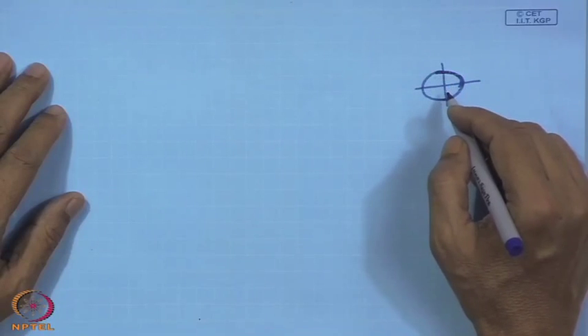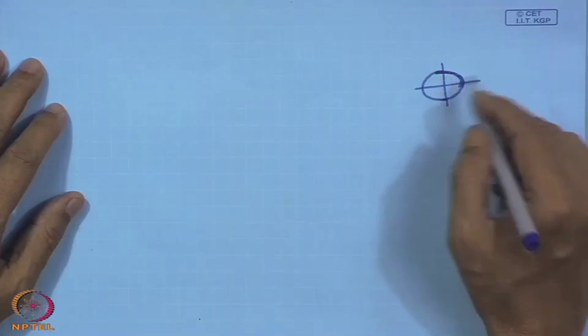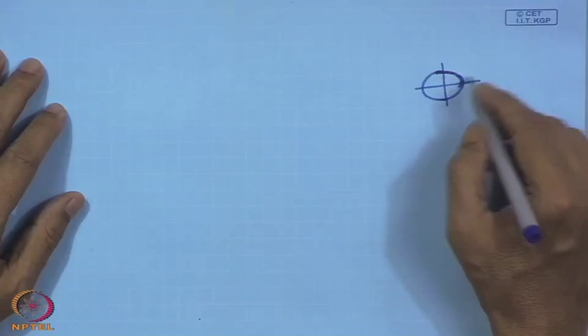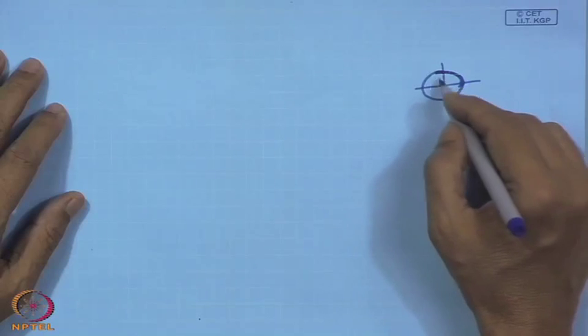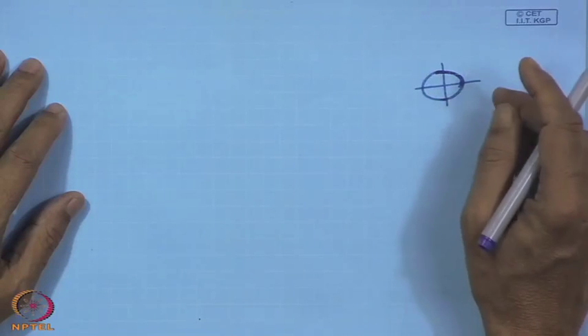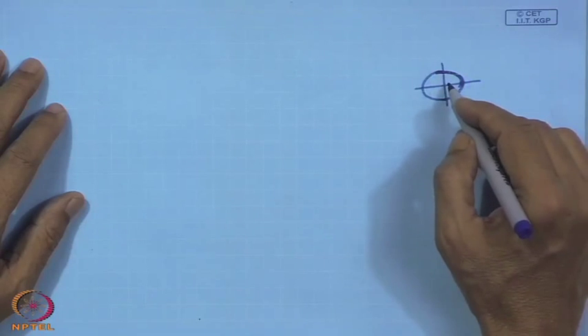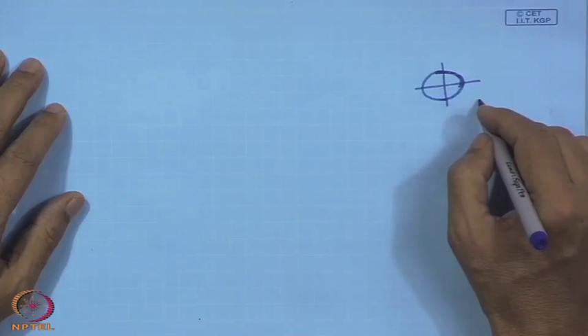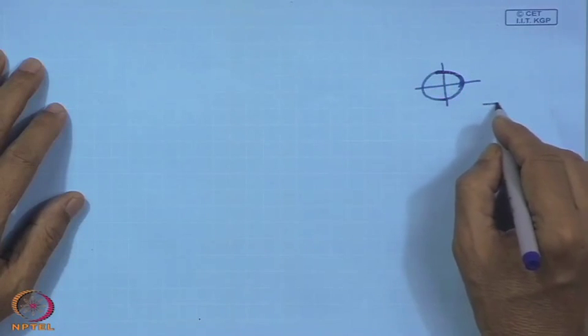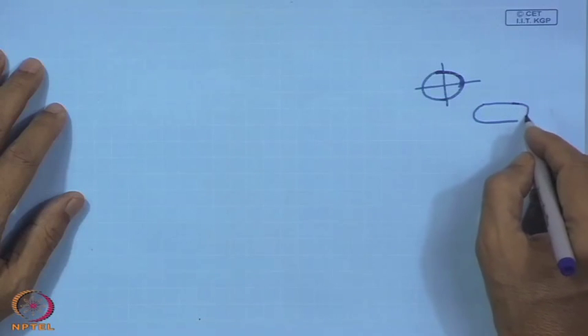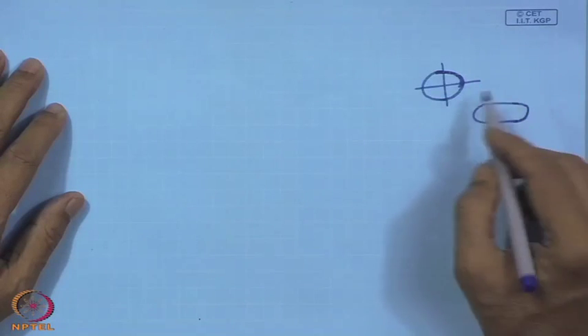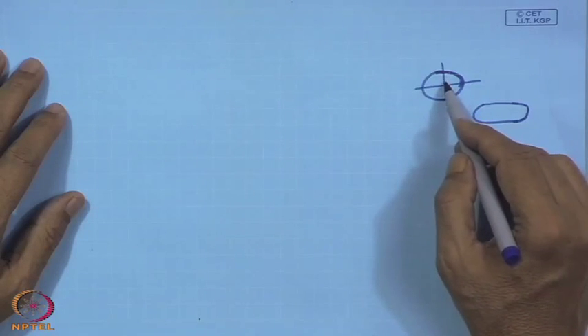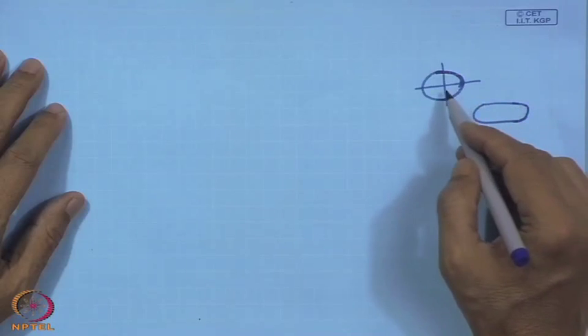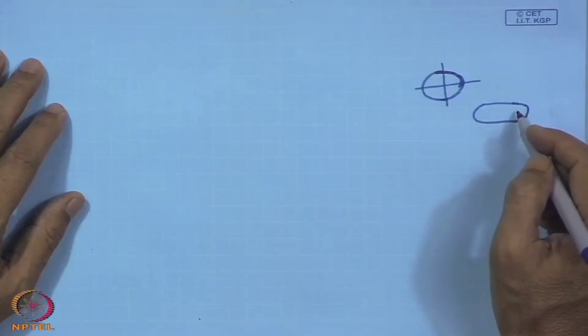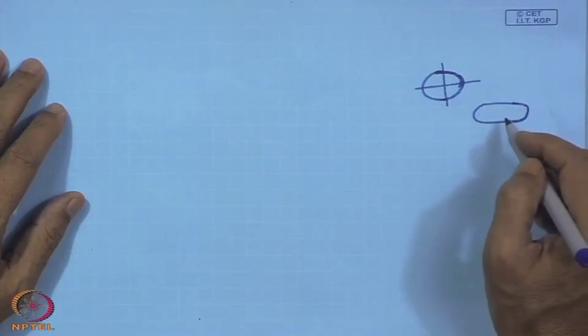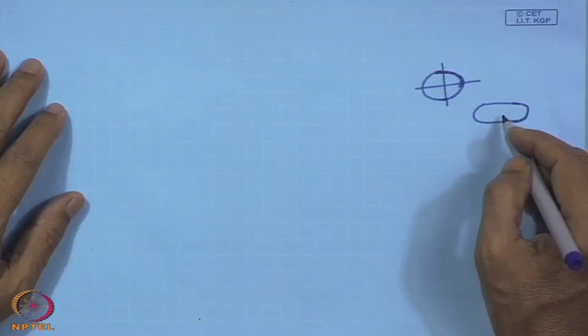When this elliptical tube is submitted to high pressure, its dimension changes and it becomes more circular in nature. That means the difference between the major axis and minor axis will be further narrowed. However, when it is submitted to high vacuum, it will be flattened and this elliptical shape will change, and then also we have some change in the dimension. So, this ellipse will either move towards a more circular form, or it will get a flattened shape, and in that case also there will be some change in dimension.